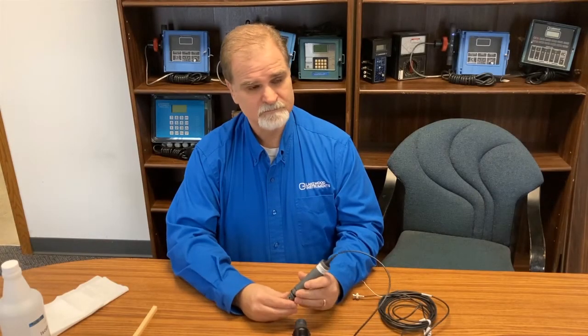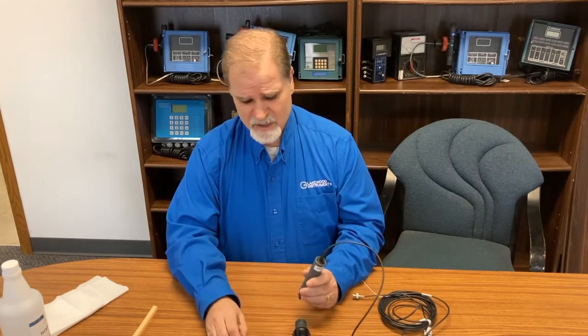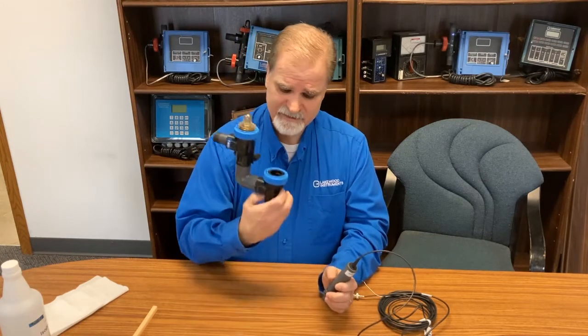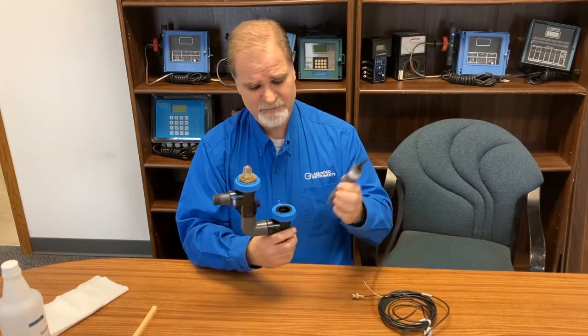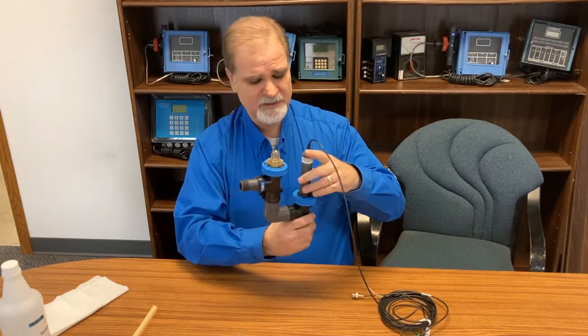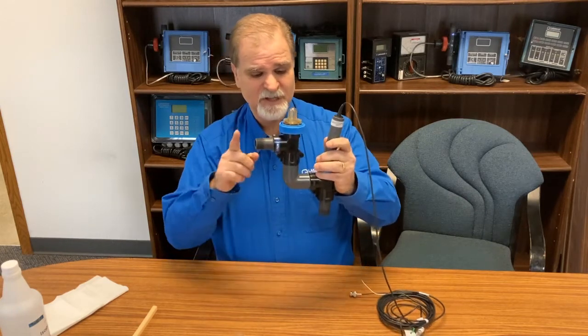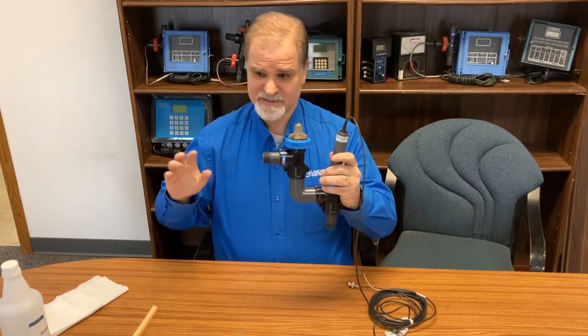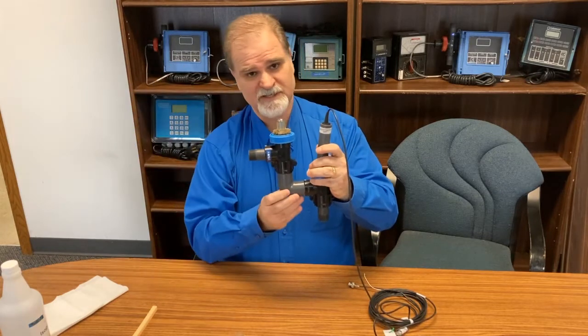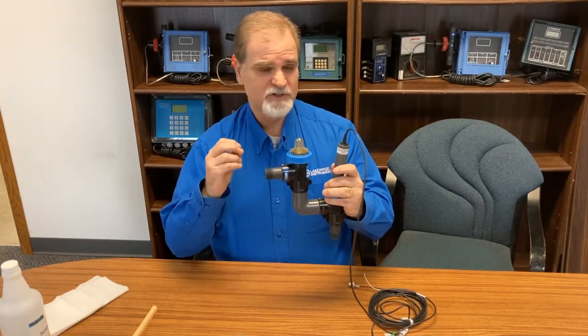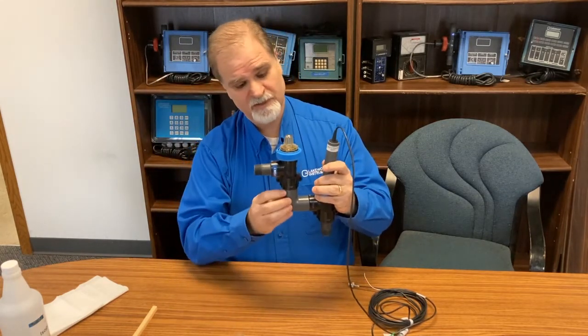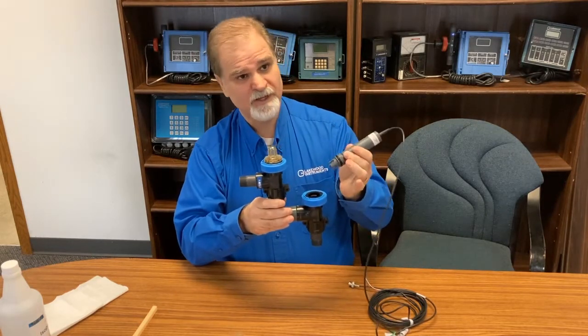So Paul, obviously we should keep the tip of the sensor wet. Yes. What about the plumbing setup and other things that could affect that? Okay. Your plumbing setup, in this case, this is a Lakewood plumbing assembly. The sensor is inserted with the glass pointed down, but this plumbing assembly should be in your system such that it's like a P-trap where it stays wet at all times. So even when you shut down the system, there will be water in the piping to keep the probe wet.